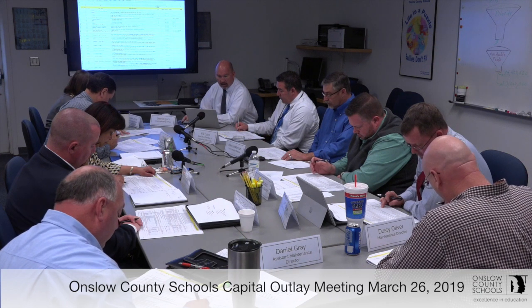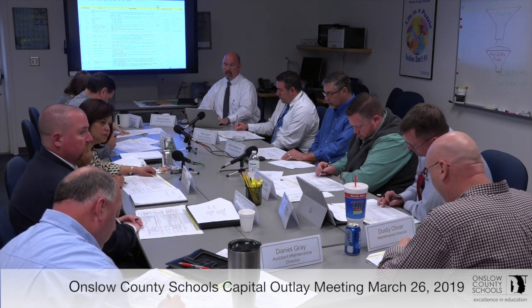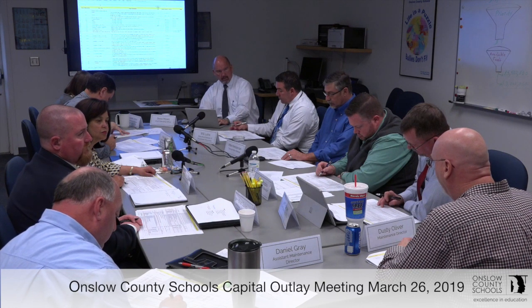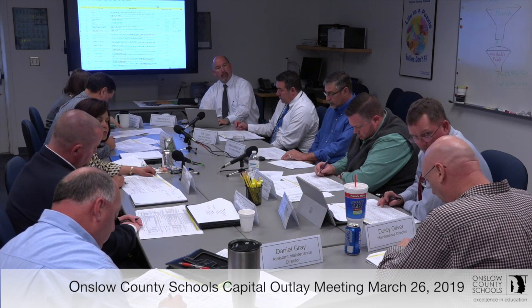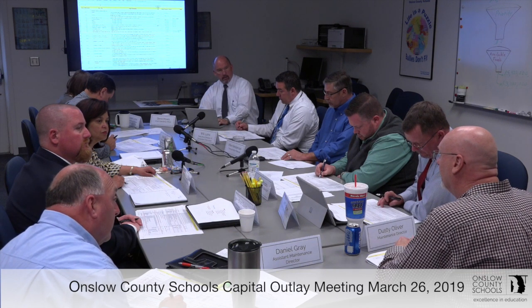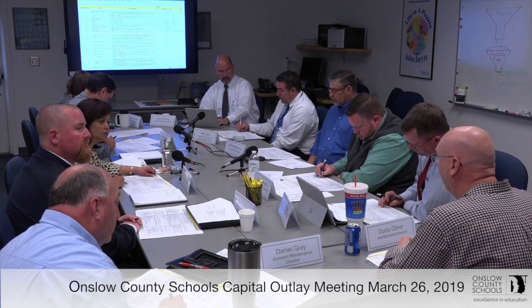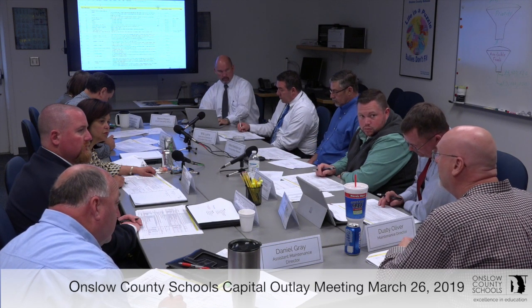Okay, replace main electrical switch gear. That continues. We continue to keep adding that, and the reason being is it works now. We do have power at the school. It's just these components are not manufactured anymore. These are just big fuses.